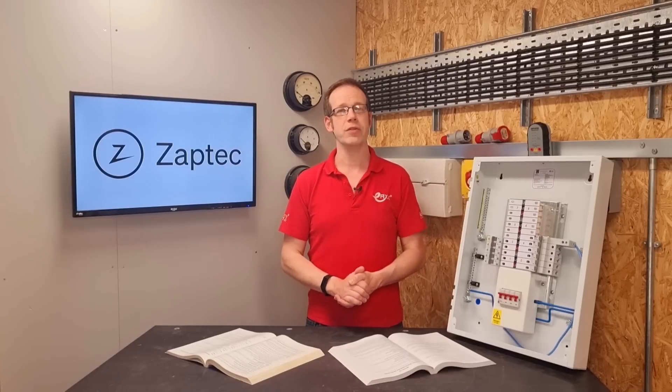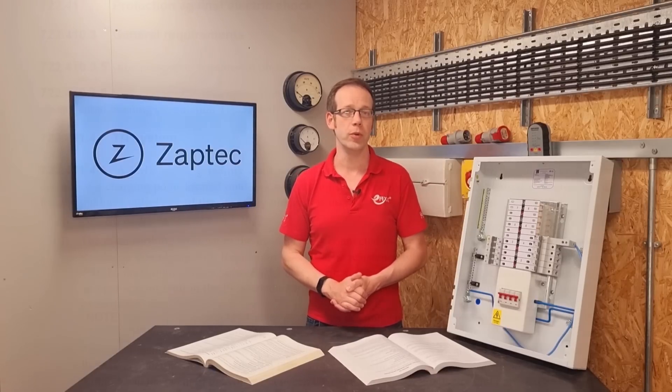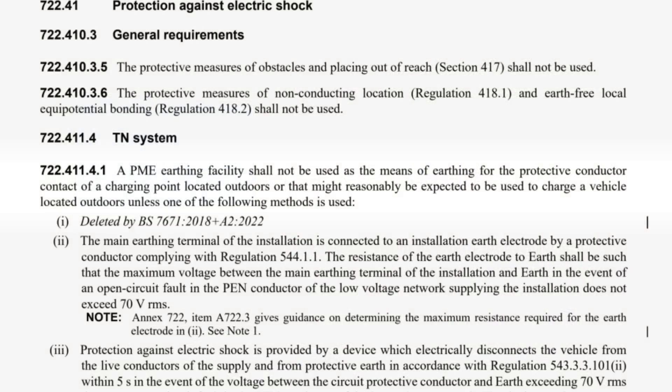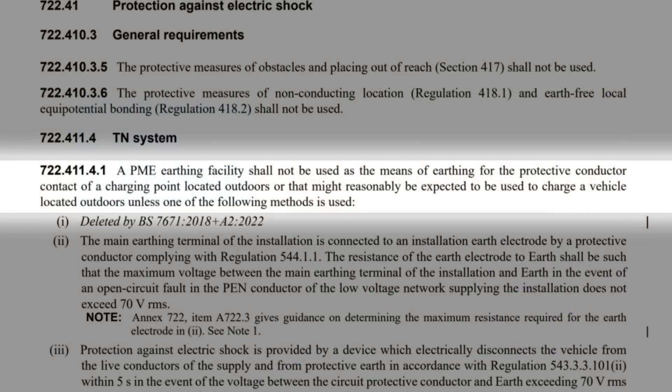Because of this, regulation 722.411.4.1 tells us that a PME earthing facility shall not be used as the means of earthing for the protective conductor contact of a charging point located outdoors or that might reasonably be expected to be used to charge a vehicle located outdoors, unless one of the following methods is used.